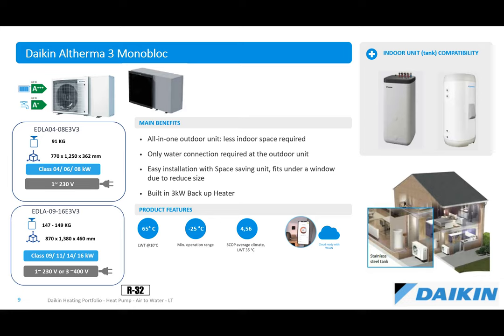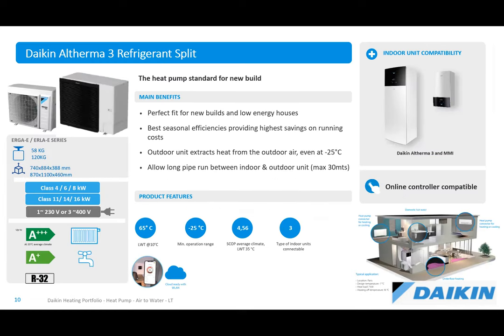So one thing to note about all of our heat pumps, they operate down to minus 25 degrees, and all of these ranges will give you a leaving water temperature of 65 degrees. So there's plenty of scope in between for fluctuations in your flow temperature.